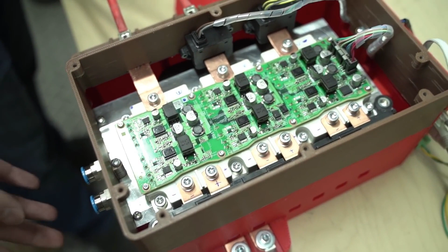The current sensors are primarily based on Hall effect elements, which inherently means they provide contactless measurement with excellent galvanic isolation. On the side of the device, there is a dedicated box containing the essential control boards, necessary control connectors, feedback connections, a separate independent power supply, and, as is customary, a standard USB interface for conveniently connecting to a computer.